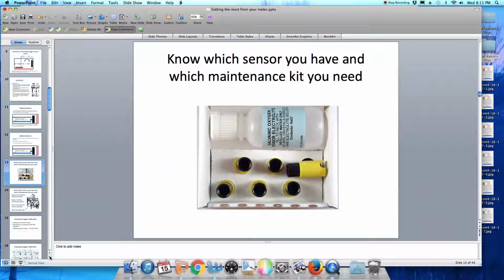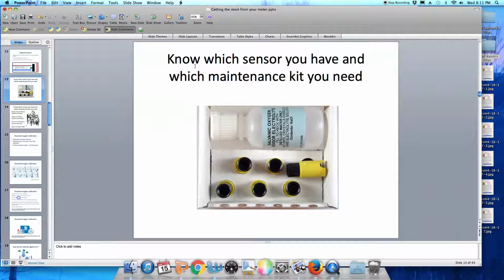Whatever kind of sensor you have, it is very important to know which maintenance kit you should need to buy. This is a YSI maintenance kit. You'll note that it is for a galvanic oxygen sensor. It has replacement membranes and it has replacement electrolyte solution. You'll fill this membrane cap combination unit with your electrolytic solution that you'll make up in this bottle and screw it on to the end of the probe to replace the membrane.